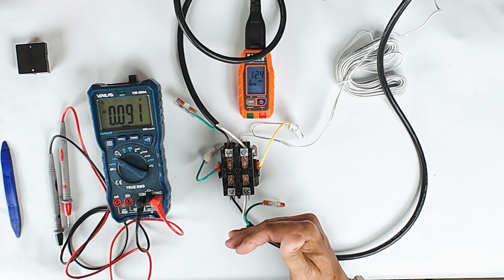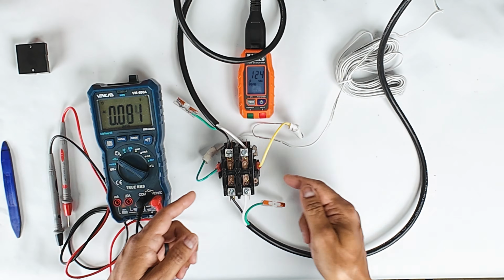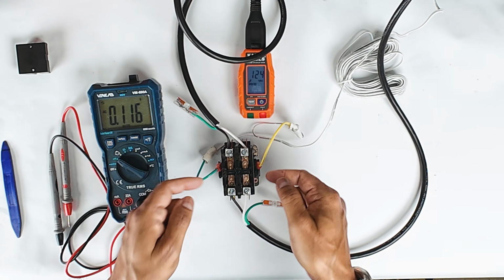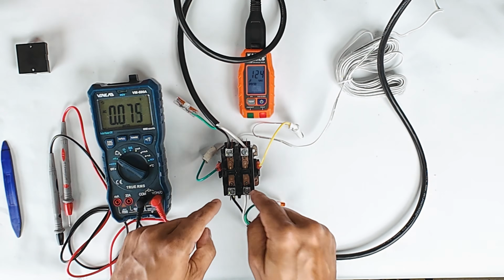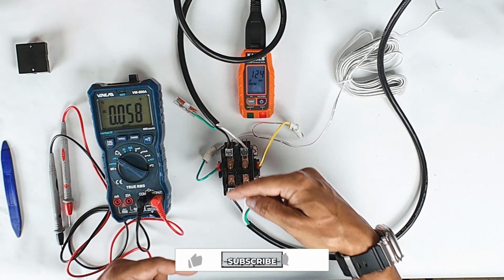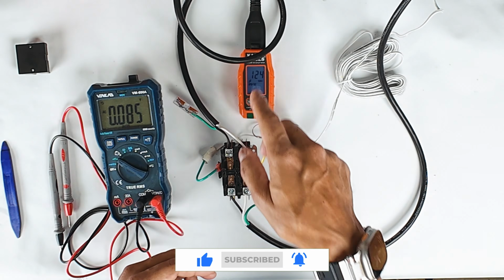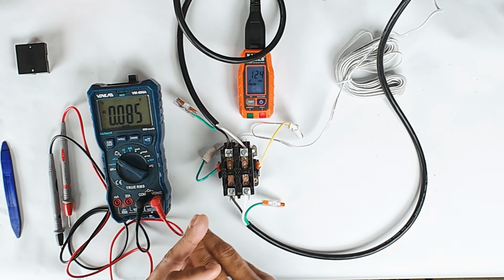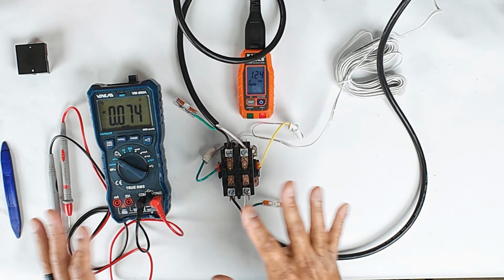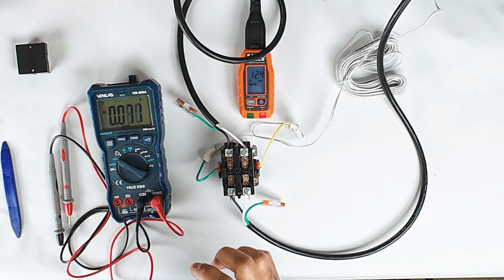So there it is. That's how it works. Power comes in. Our thermostat sends 24 volts to the coil. The contactor engages and passes the 120 volts, or the high voltage, whatever voltage you have, through to your compressor and to your fan.